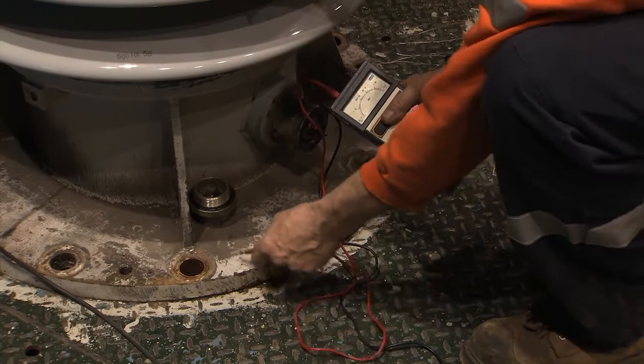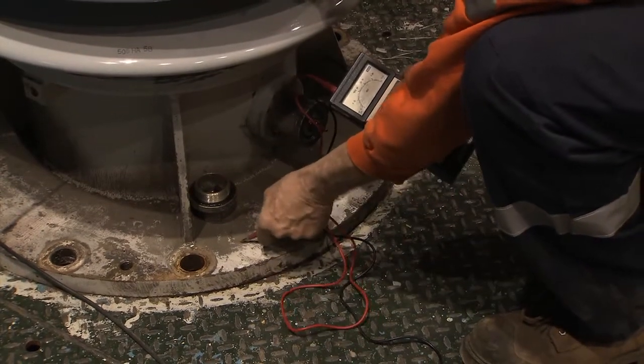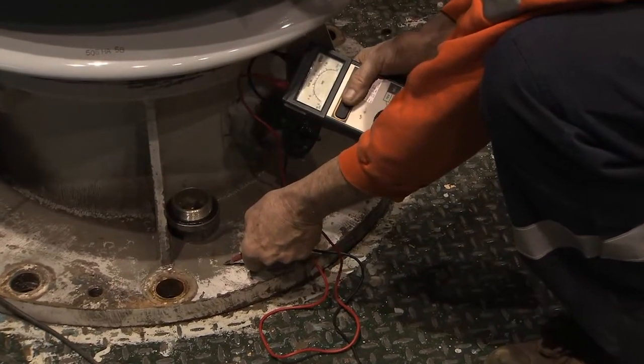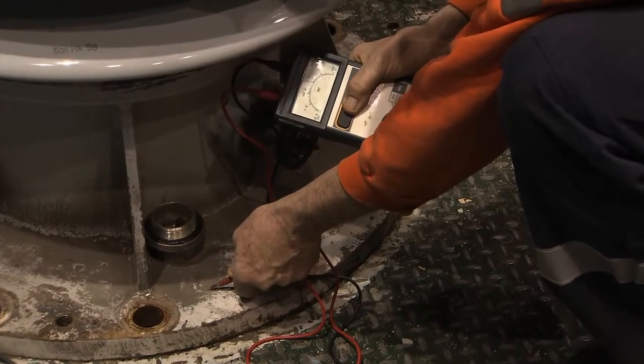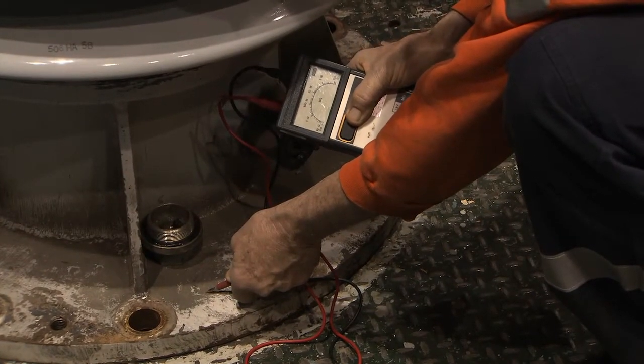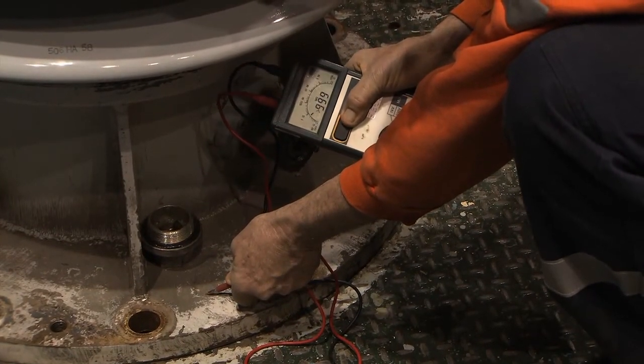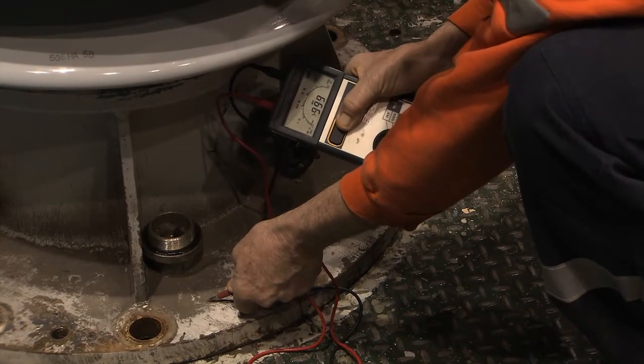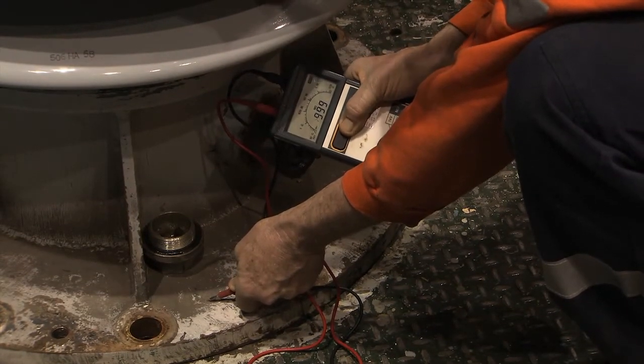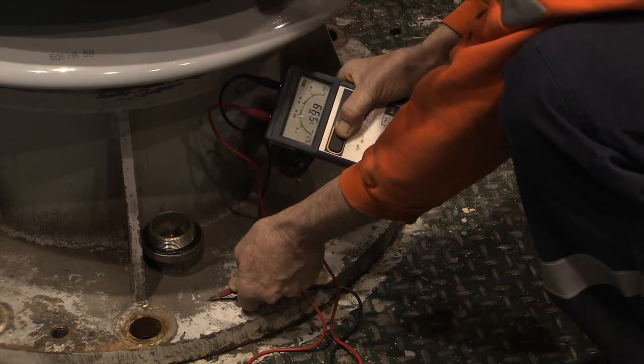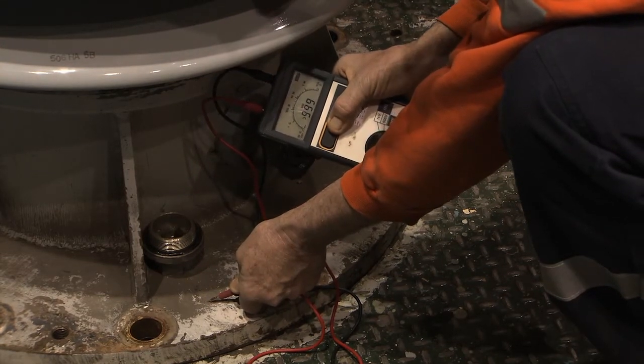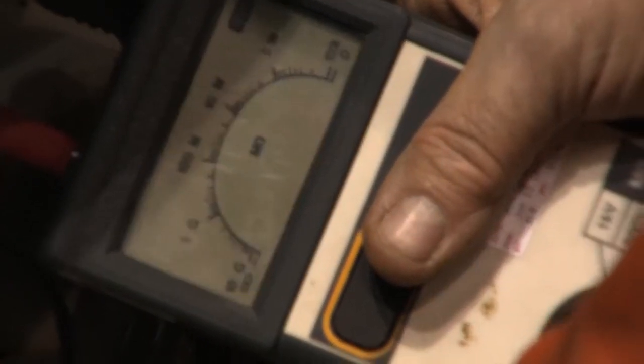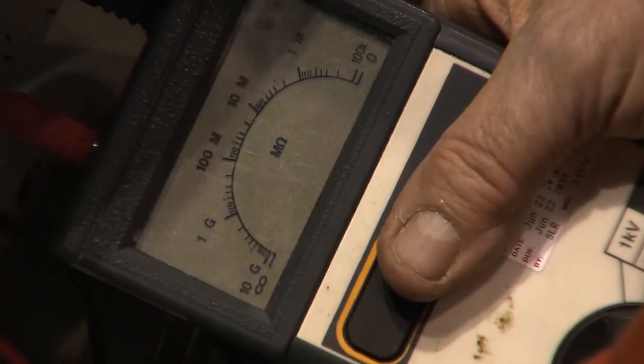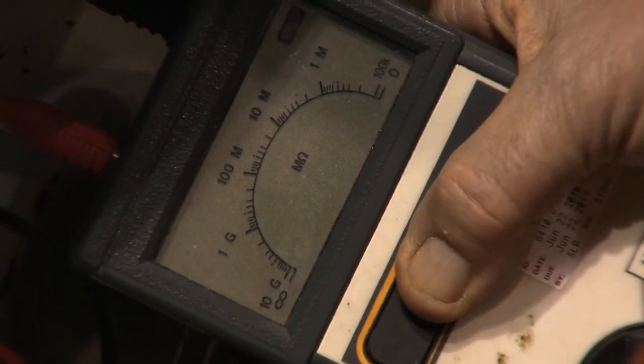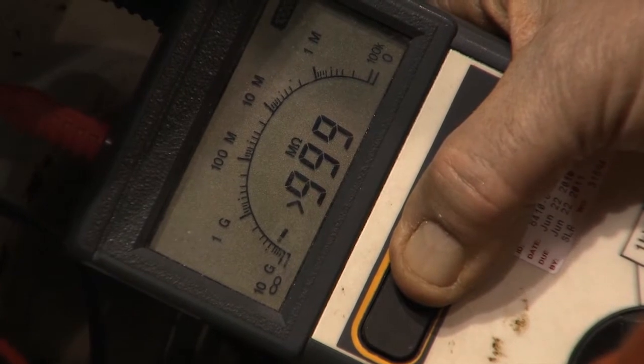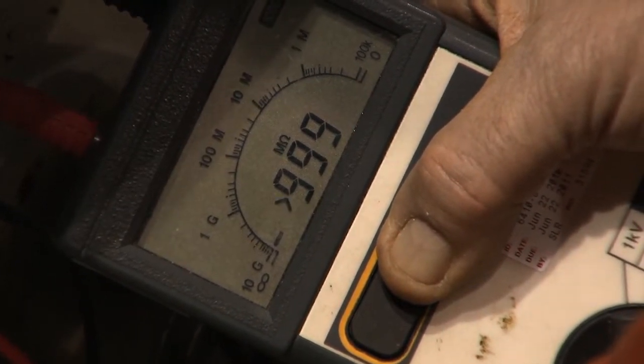After setting the selector switch located on the front of the Megger test unit to 1 kilovolt, the red lead is then connected to the bare metal of the flange of the bushing. Press the test button to activate the test voltage and take the reading digitally displayed in the display panel on the front of the Megger tester. A reading of greater than 999 megohms is a near-perfect resistance reading for the insulation in a bushing.